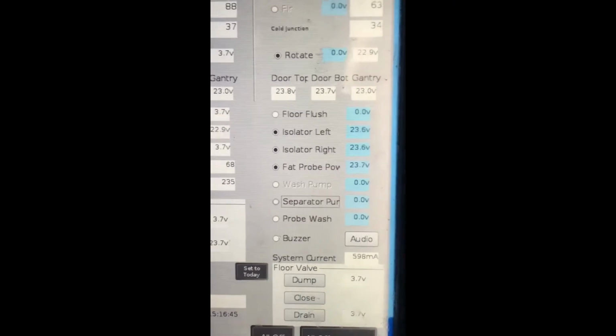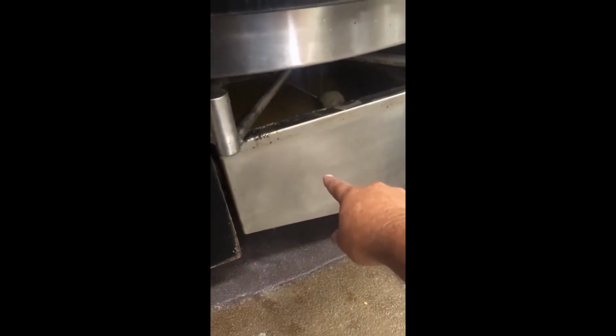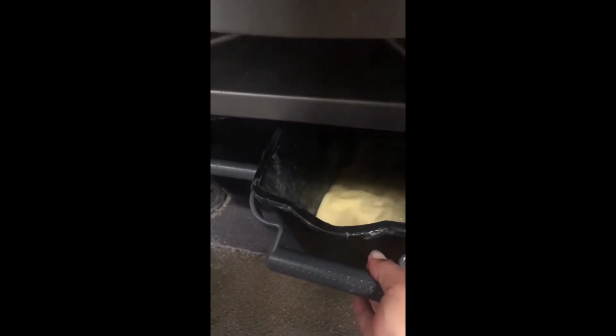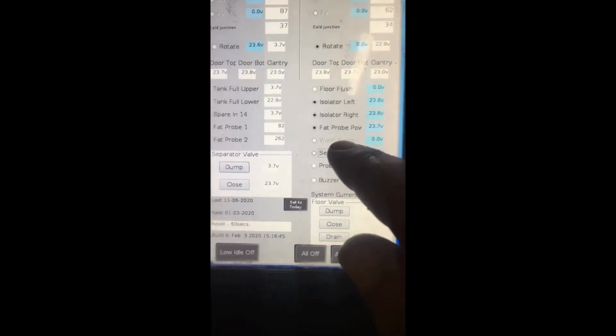Tap on it to stop. What the separator pump does is it pumps fluid from the fat separator tank to these two buckets. Run the separator pump for approximately 10 seconds. Check to make sure that fat is going into both buckets. Fat should fill both buckets evenly.